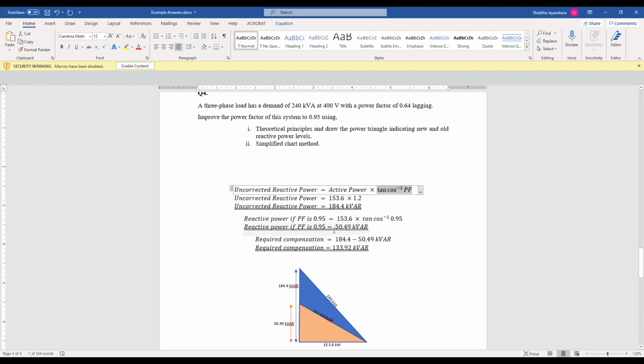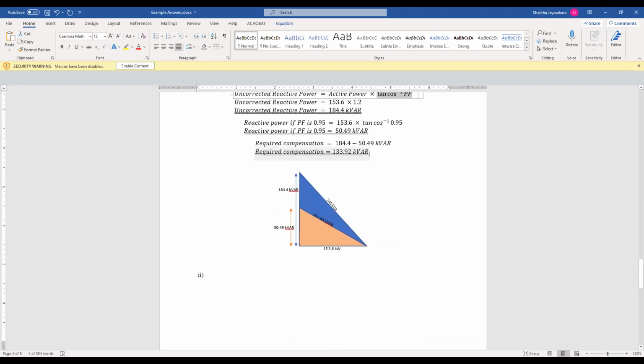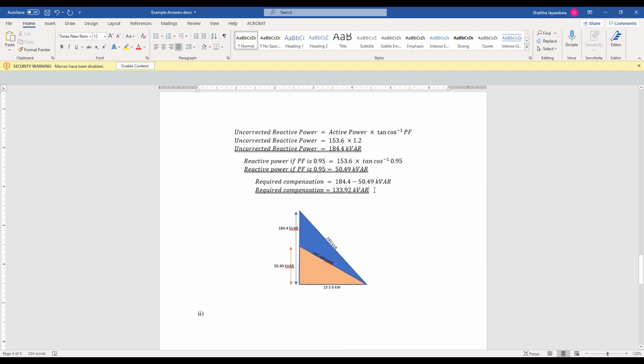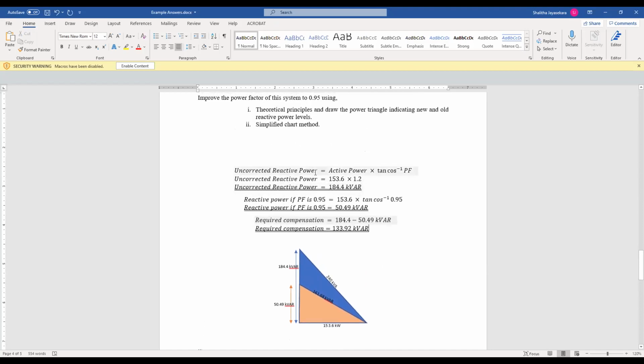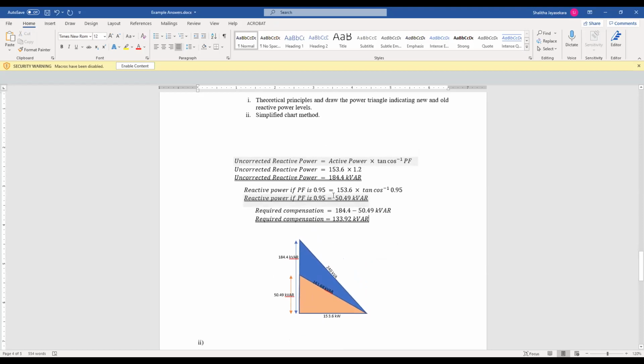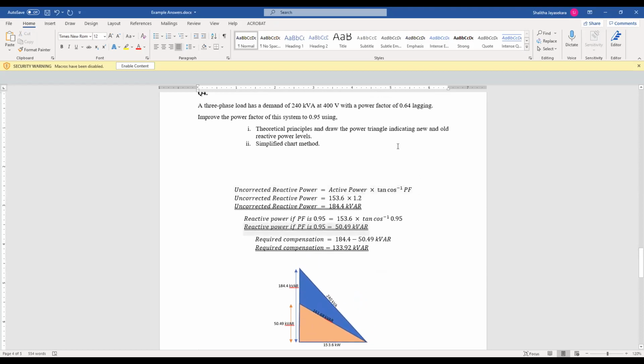So this is the current system, and this is the new system. To bring that level to this level, you need a reduction of this much, right? You can easily find this because this is the vertical component. So you can subtract these two values and find the reduction of reactive power. This is called the required compensation. So this is very easy. That's how you calculate the required compensation level using theoretical principles.